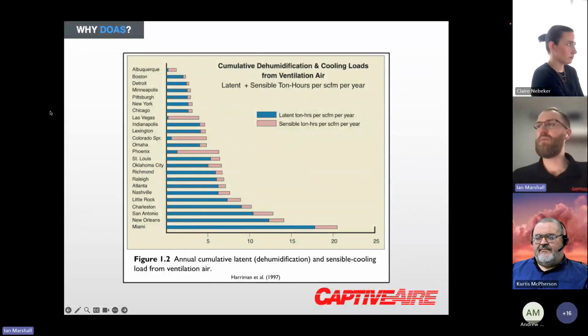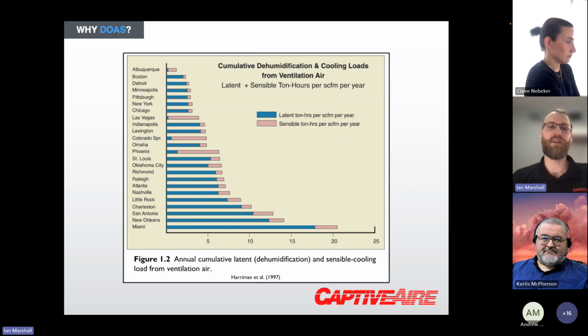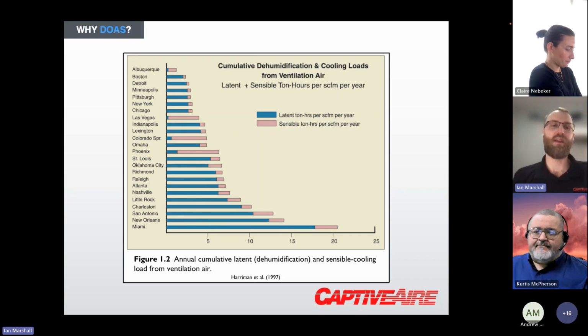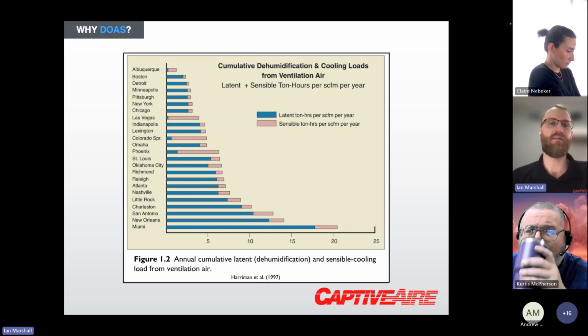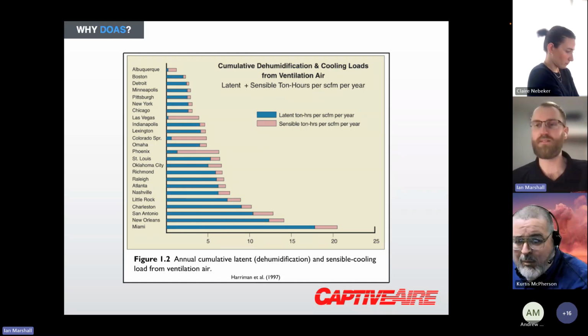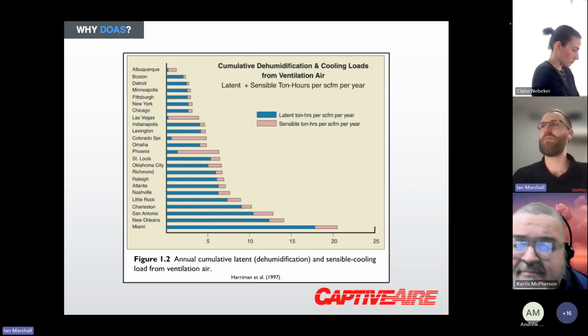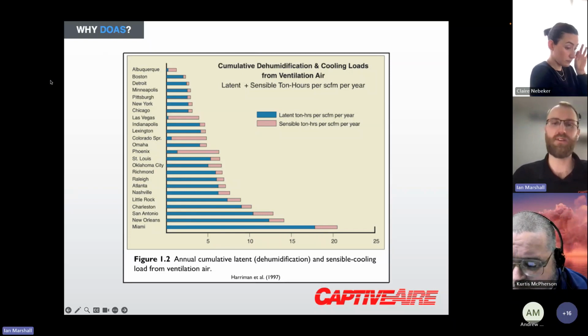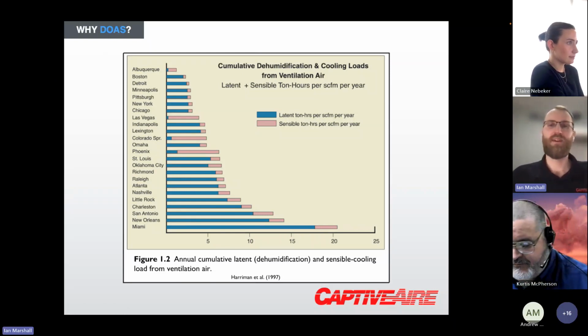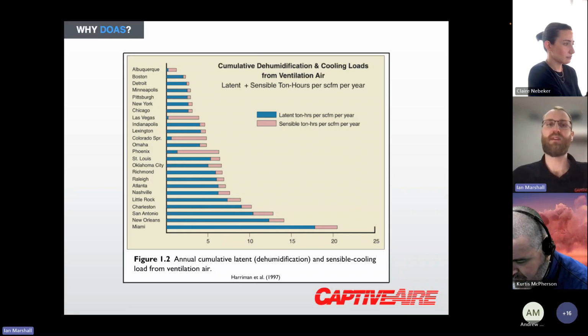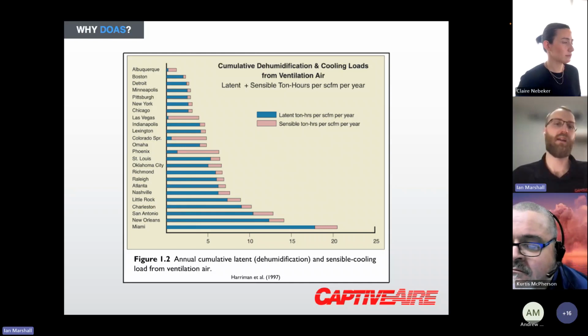So not so much, I guess, in the northwest of the country, but in general, the outdoor air loads have a large humidity load, and even in the northwest, that still is at play, to consider humidity loads. And even in places that we think of as traditionally drier locations in the country, there is still a considerable amount of latent or humidity that needs to be considered when you're talking about processing outside air. So this chart shows a different breakout of latent versus sensible cooling ton hours per year, to show how that latent or humidity removal is a demanding and energy intensive process, which is why DOAS is utilized.